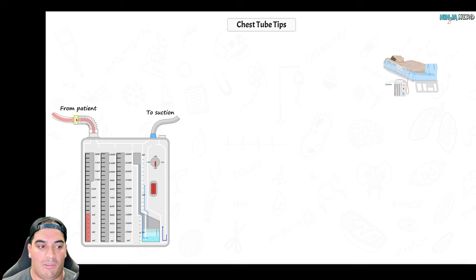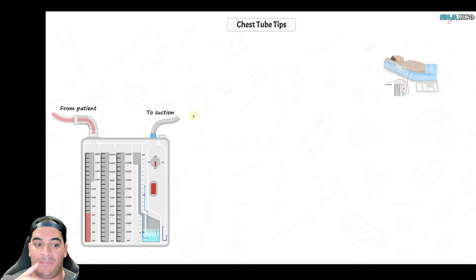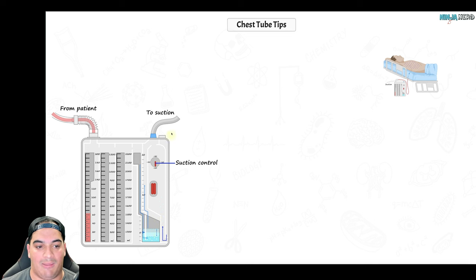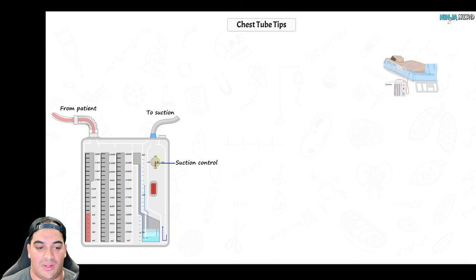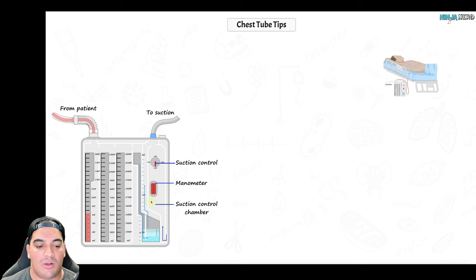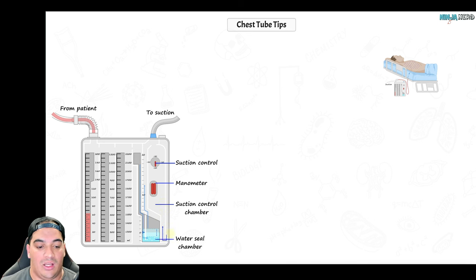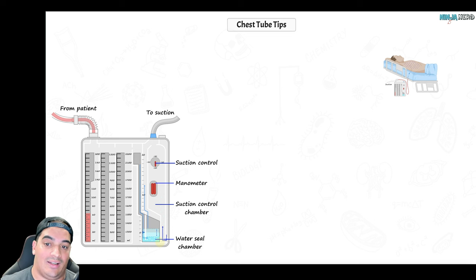The tube from the patient delivers blood, pus, or air into the collection chamber. Fluid stays there; air moves into the water seal chamber, where it bubbles through water and is prevented from flowing back toward the patient. The suction control chamber is filled with water to regulate the degree of suction, typically set to negative 20 cmH2O.